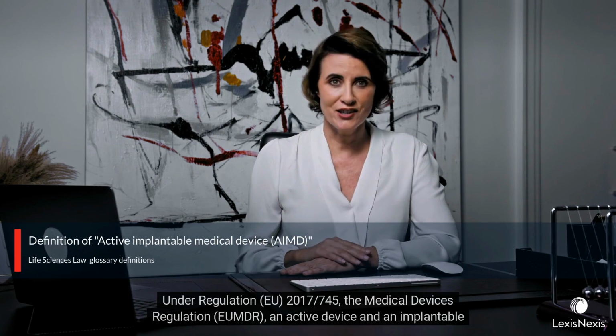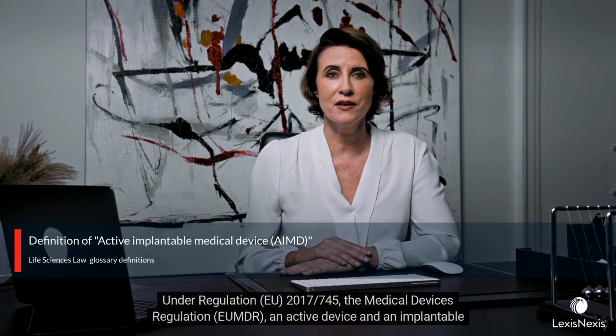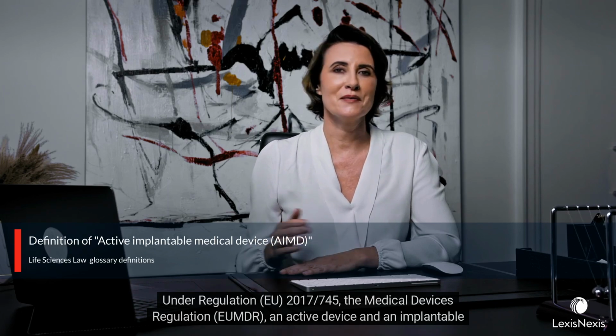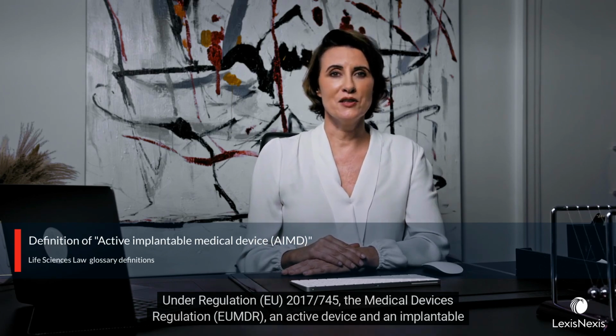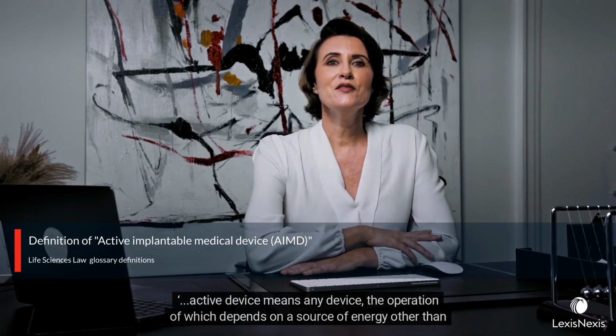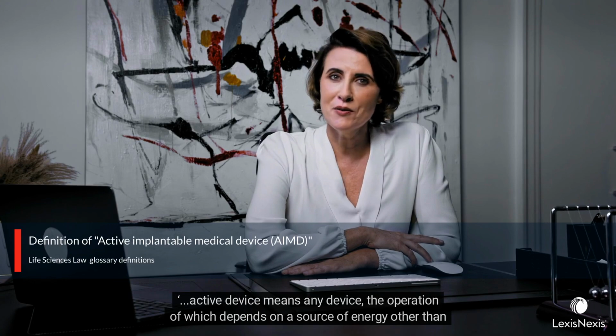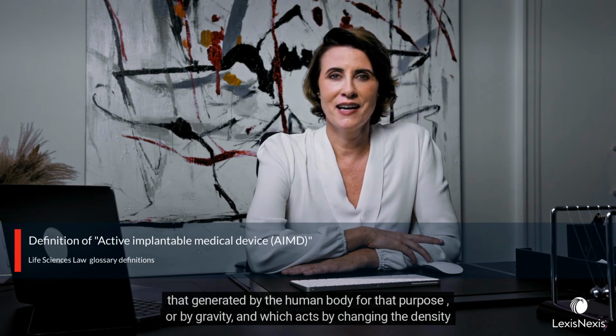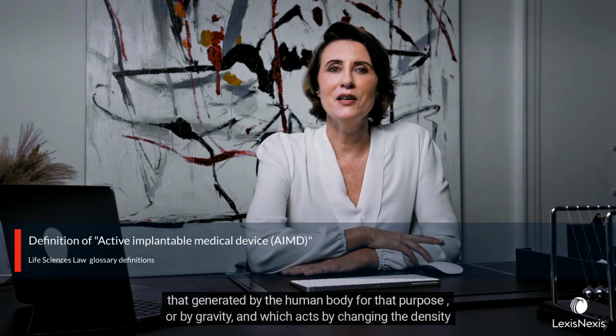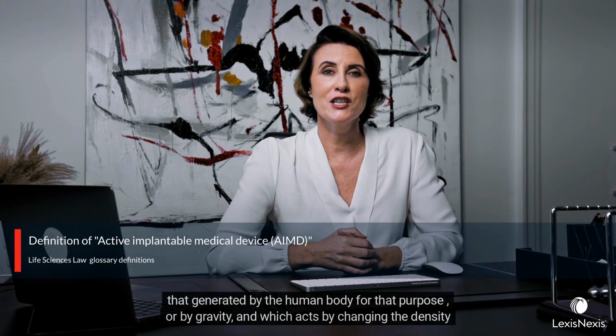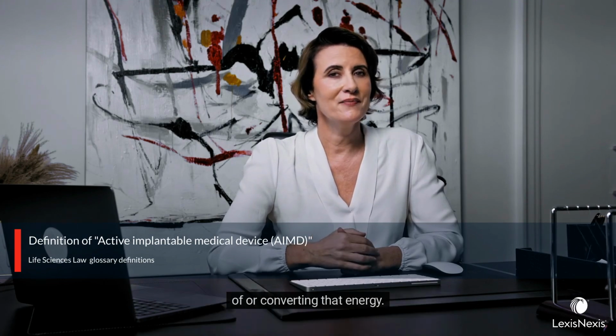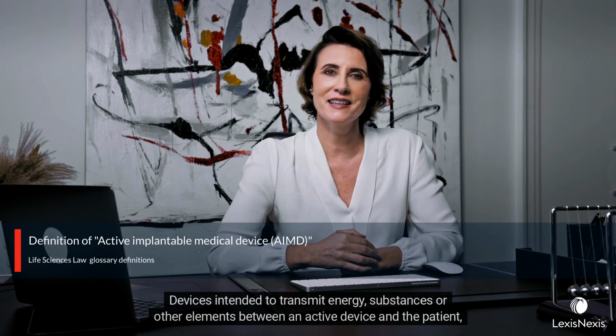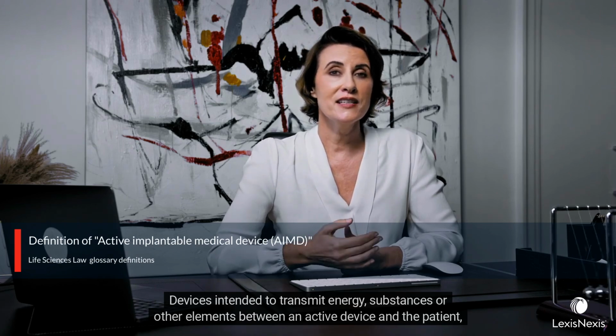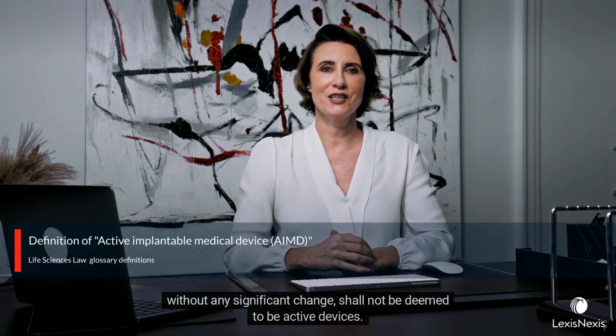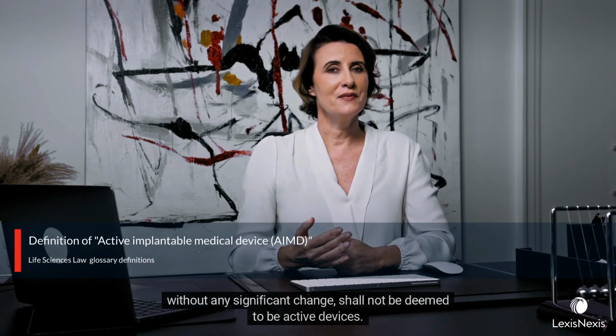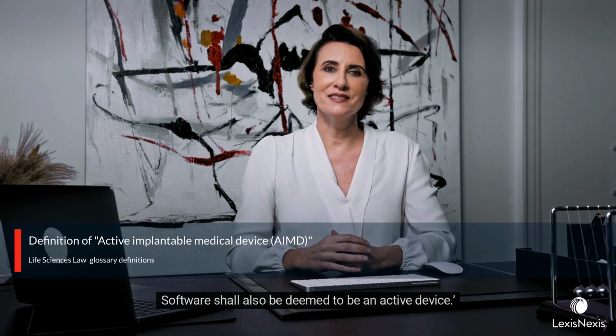Under Regulation EU 2017/745, the Medical Devices Regulation, EU MDR, an active device and an implantable device are separately defined. Active device means any device, the operation of which depends on a source of energy other than that generated by the human body for that purpose or by gravity, and which acts by changing the density of or converting that energy. Devices intended to transmit energy, substances, or other elements between an active device and the patient without any significant change shall not be deemed to be active devices. Software shall also be deemed to be an active device.